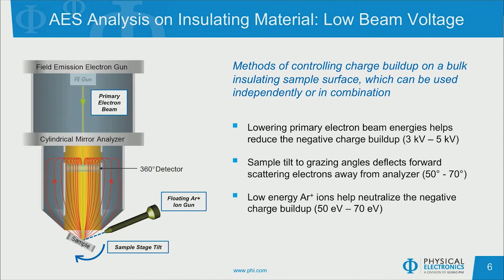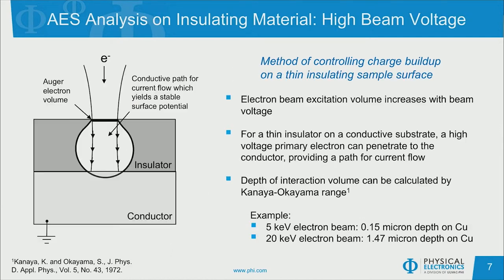A few examples of methods used to handle charge compensation for insulating samples in Auger analysis are shown here using low beam voltage techniques. One way to reduce the negative charge buildup is to use a lower primary electron beam on the order of 3 to 5 kilovolts. Another approach is to tilt the sample to grazing angles to deflect the forward scattering electrons away from the analyzer. We can also use a low energy argon ion flood to help neutralize the negative surface charge. Another technique uses high electron beam voltages: if we have a thin insulating layer on top of a conductive substrate, we can use a high electron beam energy to punch through the insulator to form a conductive path. The depth of the interaction volume can be calculated from the Kanaya-Okayama range equation.